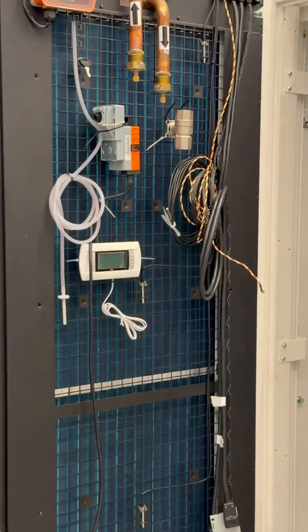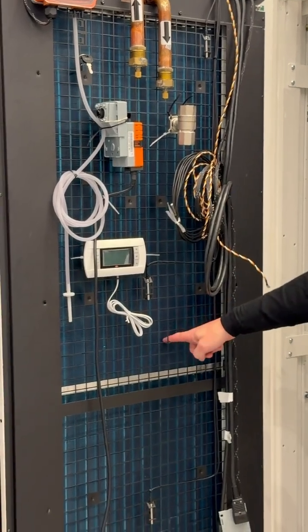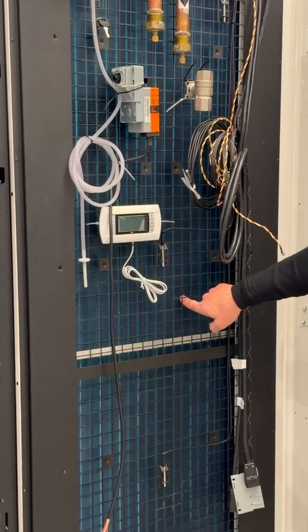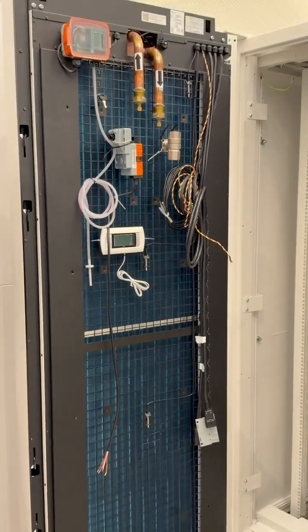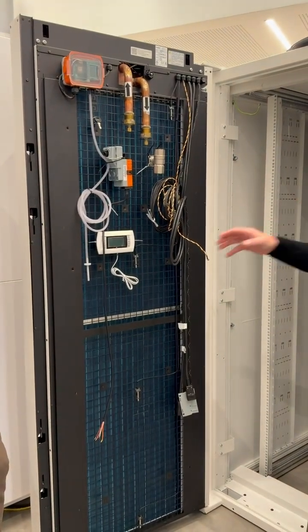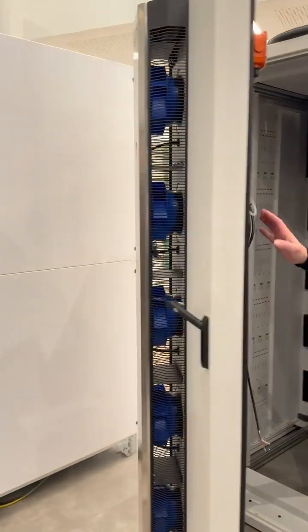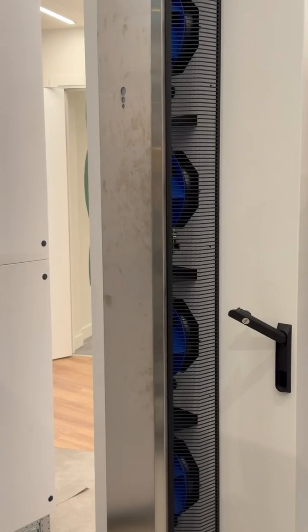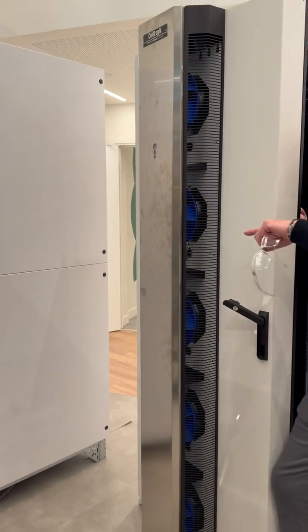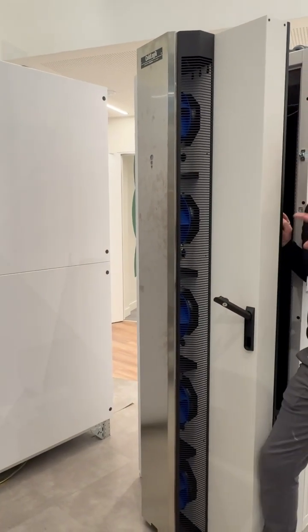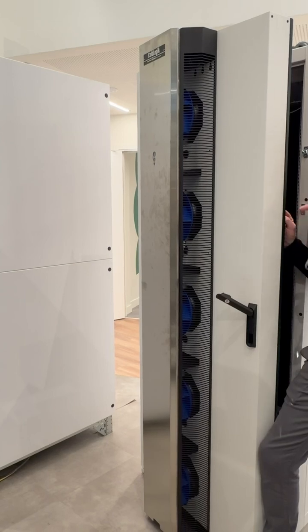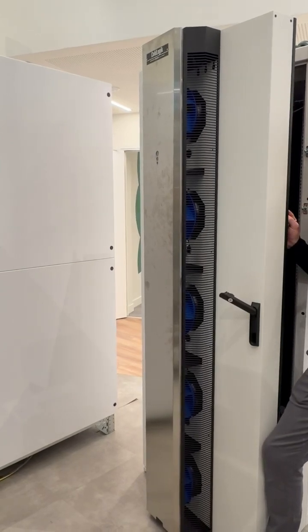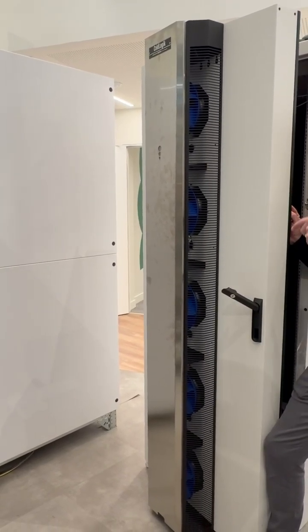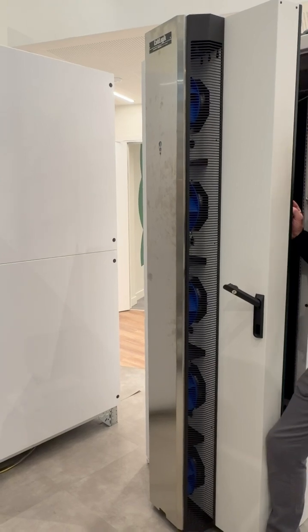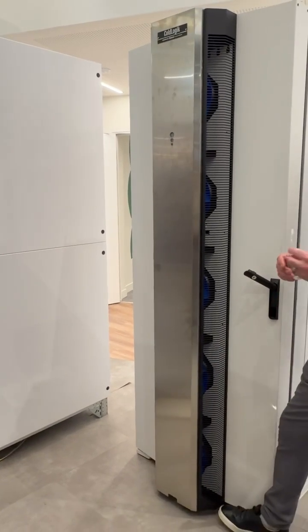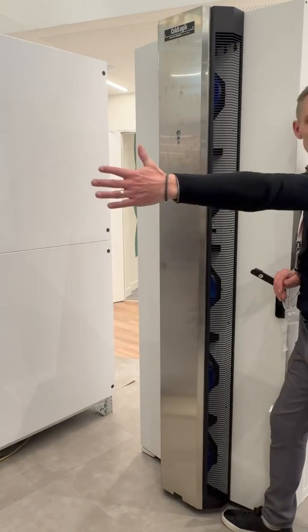So the heat comes off the back of the servers, hitting the coil. There's thousands of capillaries in there, so it goes all the way around, cools that temperature down, and then spits out the side. So we have what we class as reverse centrifugal fans. What that means is we operate at a lower power density for the fan, but it gives optimal performance. So what that means is you'll see some other rear doors in the industry that have fans sitting here and they're just pumping straight out.